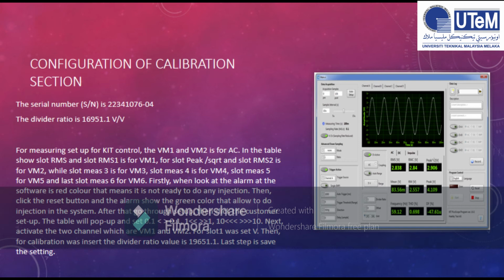Firstly, when look at the alarm at the software is red color. That means it is not ready to do any injection. Then click the reset button and the alarm show the green color that allow to do injection in the system. After that, go through setup, then click the customer setup. The table will pop up and set the 0.1, 1, 10.